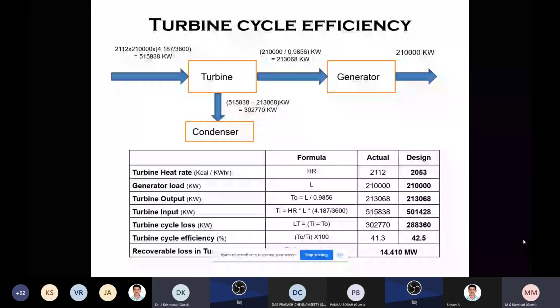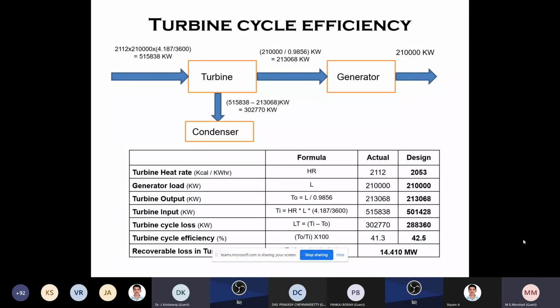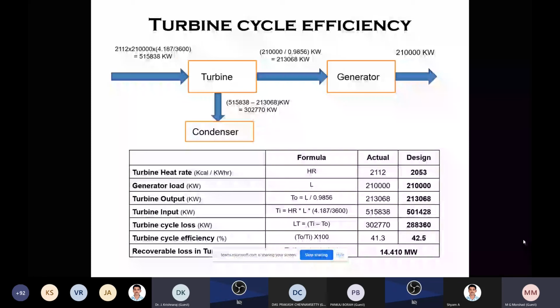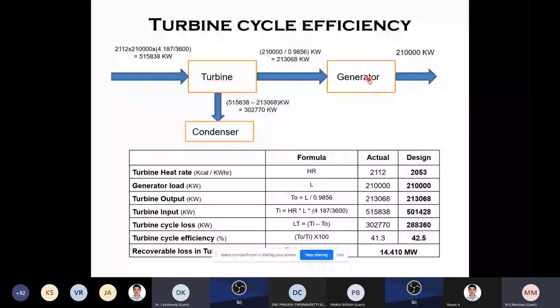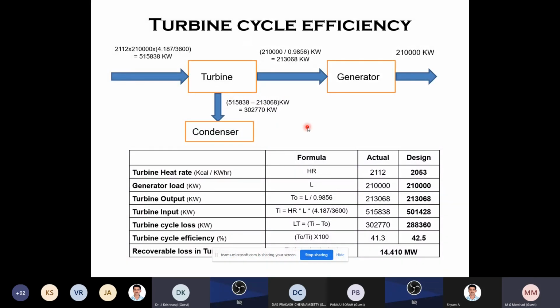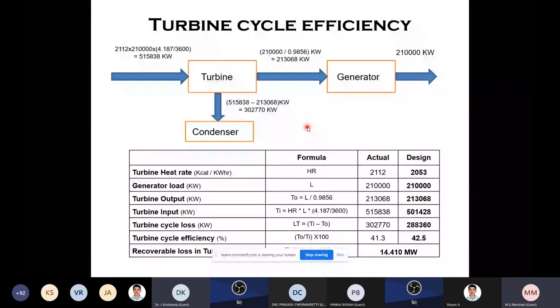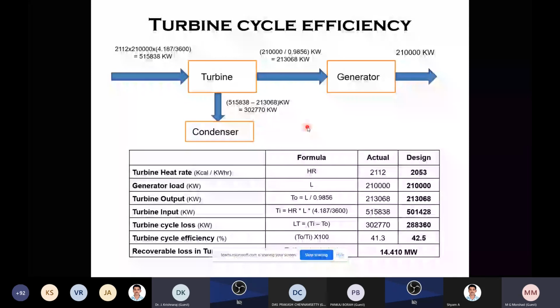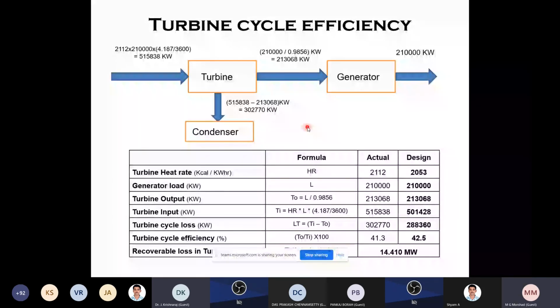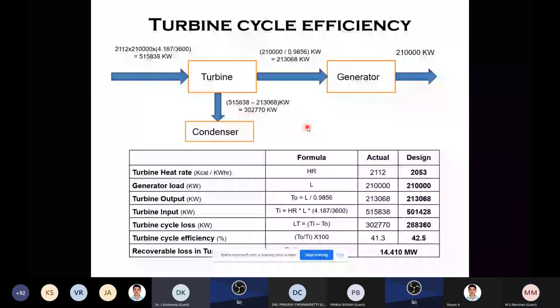Now, another thing is the turbine cycle efficiency. I would say turbine efficiency and turbine cycle efficiency are entirely different. The cycle consists of the turbine, generator and condenser. The majority of the heat energy is lost in the condenser through the cooling tower. Normally the turbine cycle efficiency will be around 40%, and 60% goes to the atmosphere through the cooling tower. The majority of the heat is lost there.